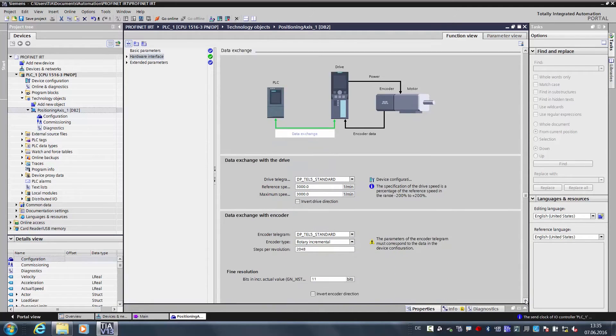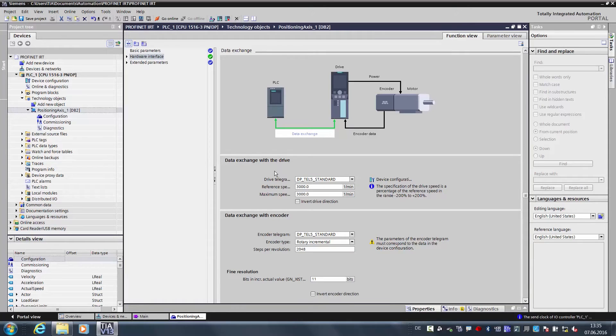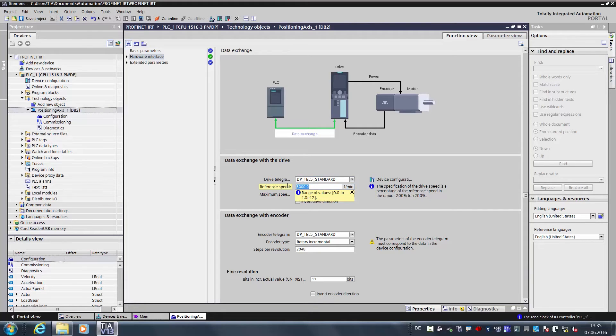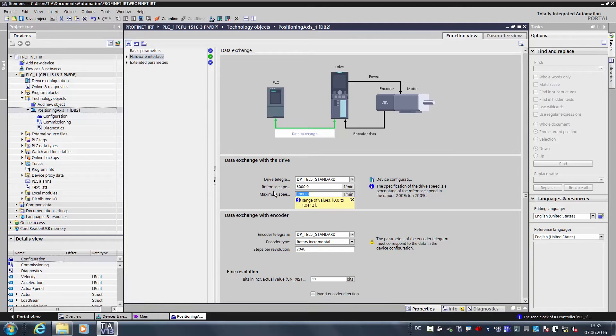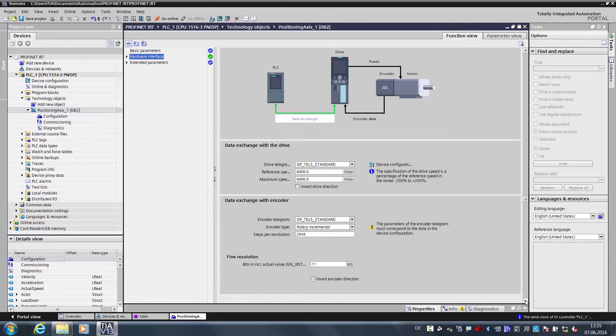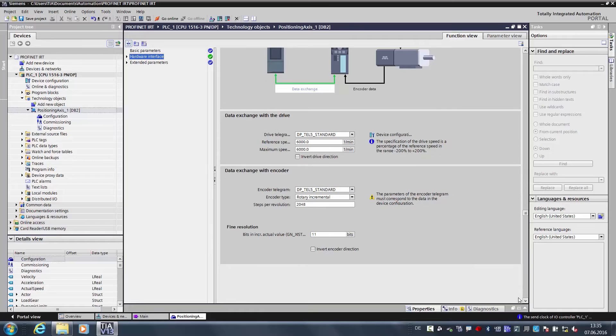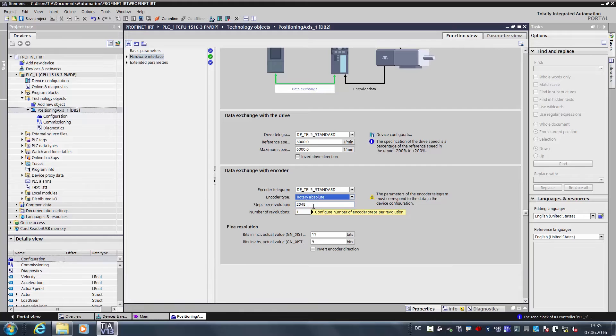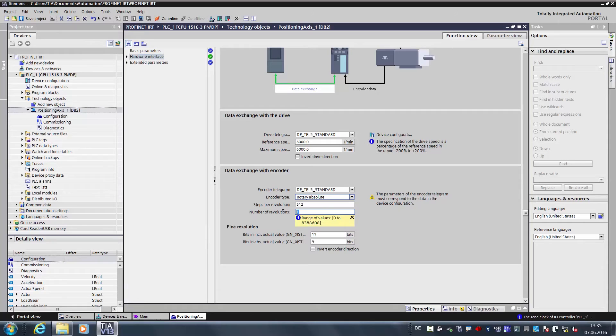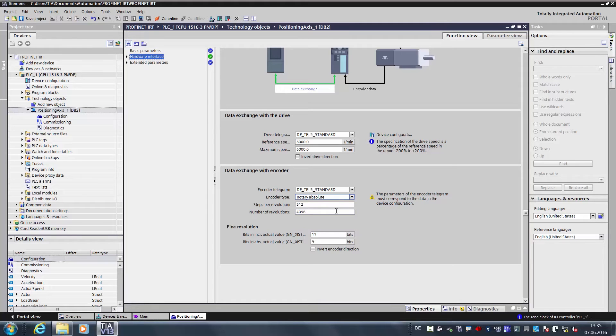We now move further down to the data exchange. Here we see that PROFIDRIVE TELEGRAM 5 is the default setting. This is the telegram that you also need for isochronous communication. Now you still have to specify the reference speed and the maximum speed. Because I have already put the drive into operation, I know that the configuration there is 6000 rpm. The sensor also communicates via the PROFIDRIVE TELEGRAM 5. Except there is no rotational sensor installed in the red axis in our test box, but rather an absolute encoder. The sensor has 512 increments, an absolute, in other words, multi-turn resolution of 4096, and the fine resolution is correct, so I don't have to change anything here.